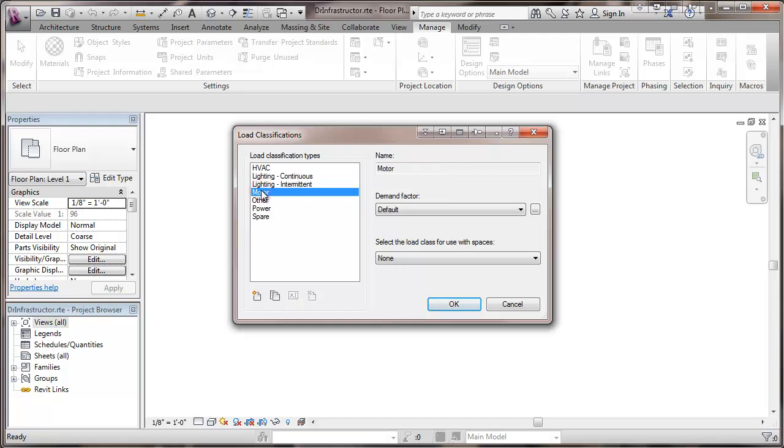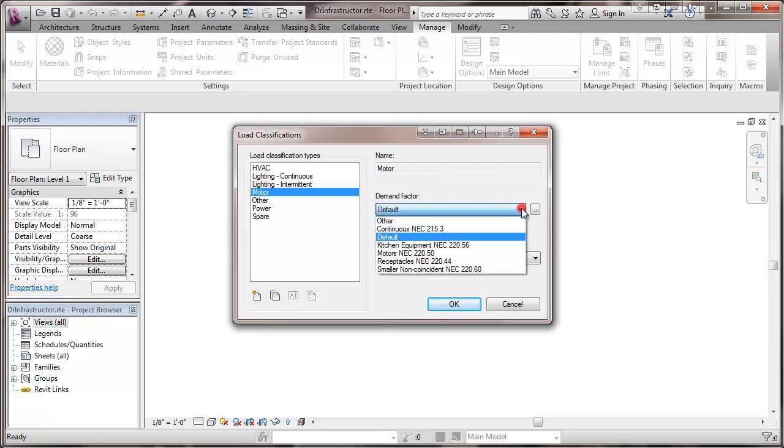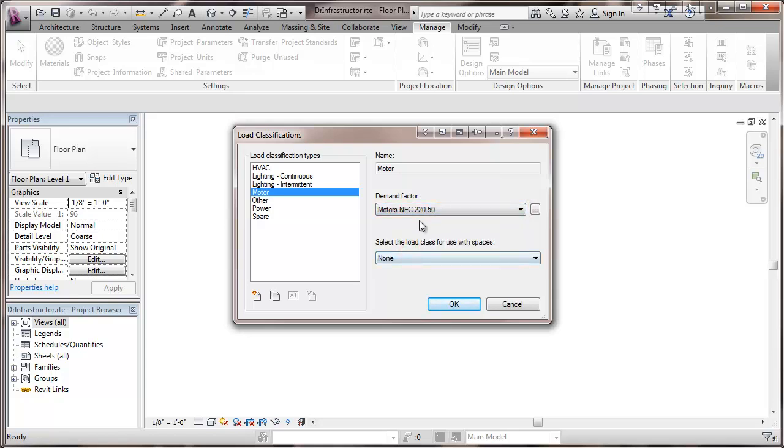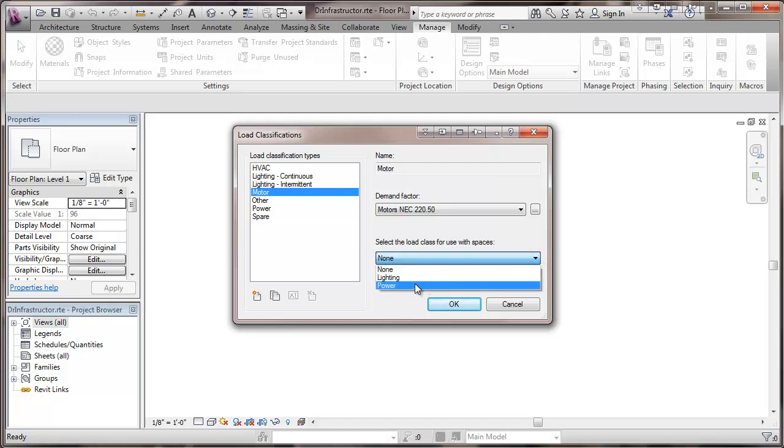For our motor loads we're going to pick up a demand factor here that we previously set up. It's basically 125 percent of full load current of the motor and feeders. It would be the largest motor at 125 percent the rest at 100 percent. I'm going to put those motors under the power category.